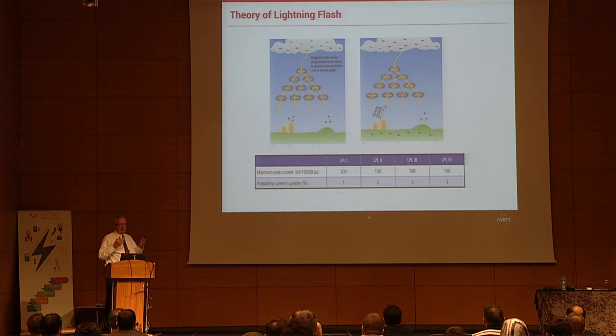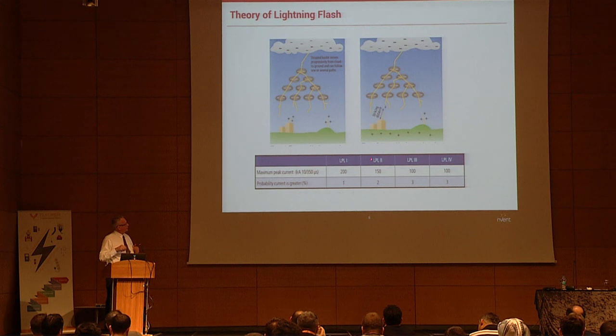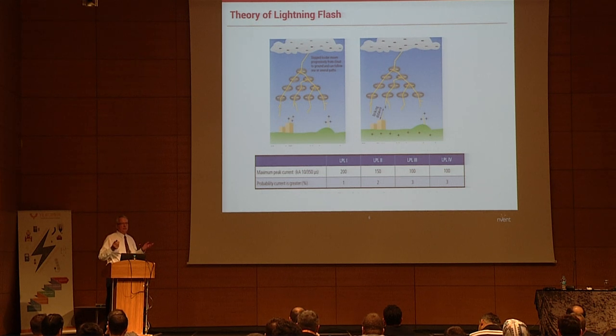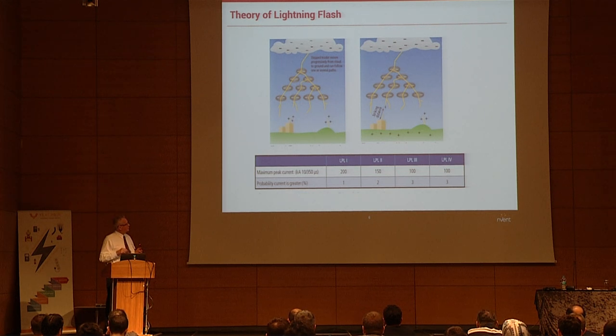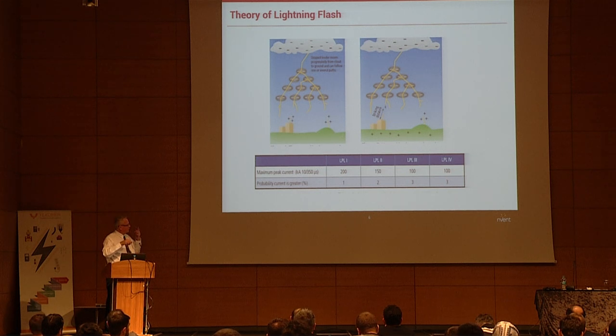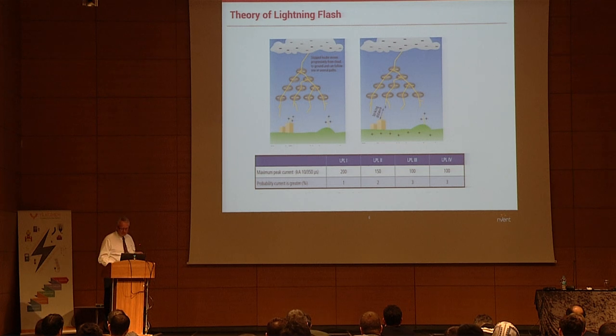The connection drains the energy into the ground. Everything is connected and related to lightning protection levels and the currents associated with them. For lightning protection level one, the most conservative approach, I have 200 kiloamps of current. When I go to protection level four, that's 100 kiloamps — still a lot of energy.